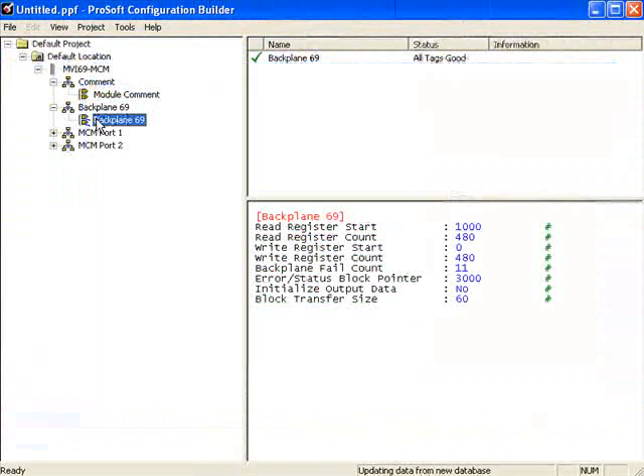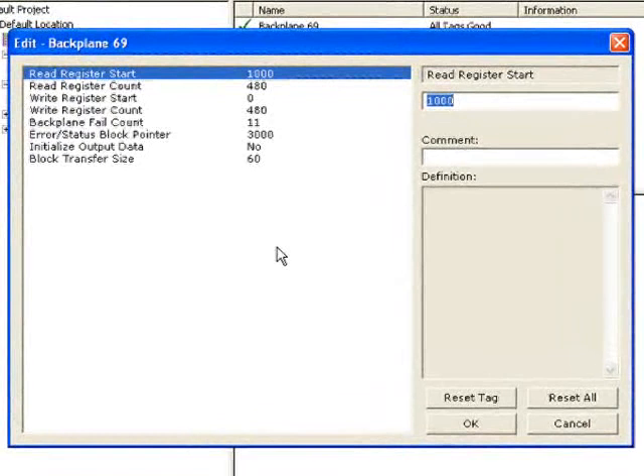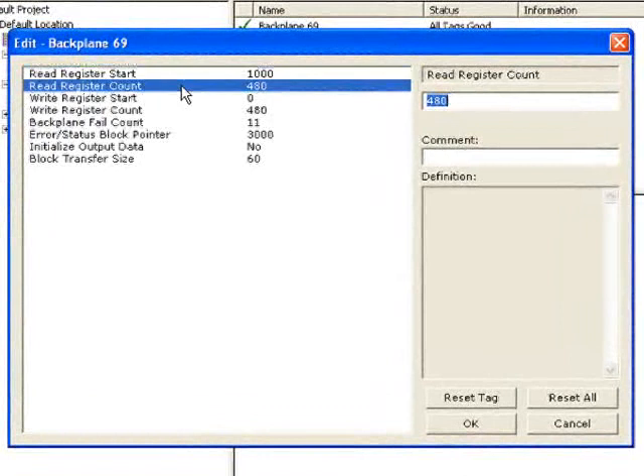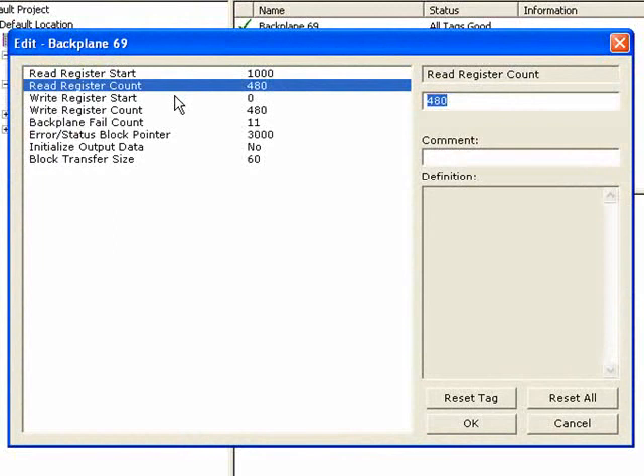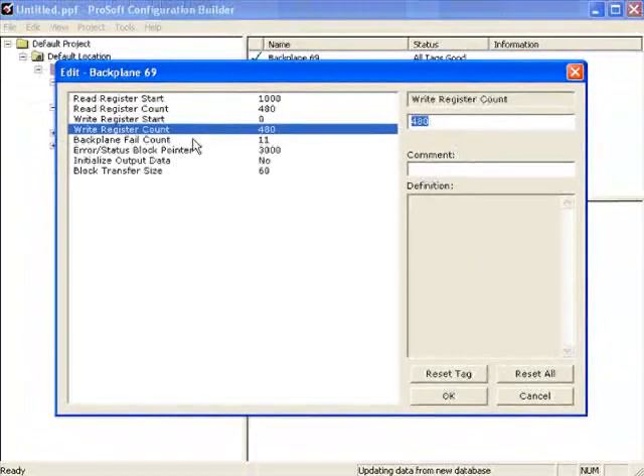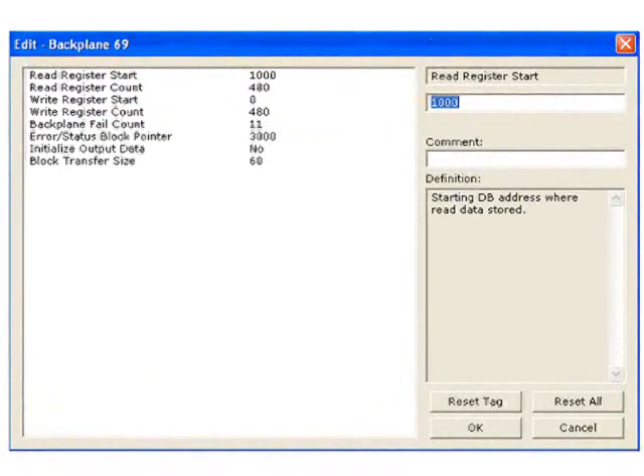Expand the Backplane69 section and click on Backplane69. From here, we can double-click on it to change the parameters. Here we have the Read Register Start — that's the starting address of data within the module that will be going to the CPU. The Read Register Count is how many of those read registers are going to the CPU. The Write Register Start is the location where the module places data that comes from your CPU.